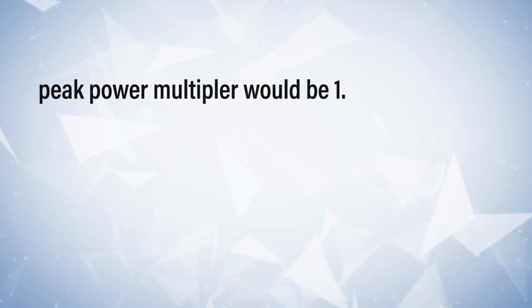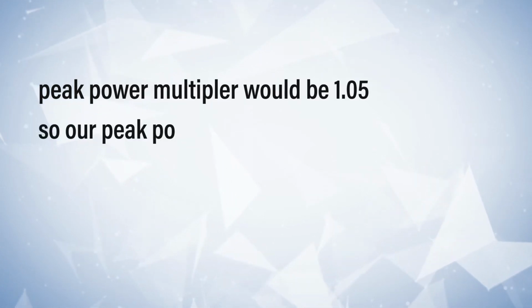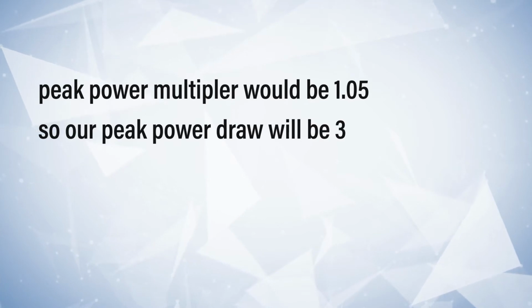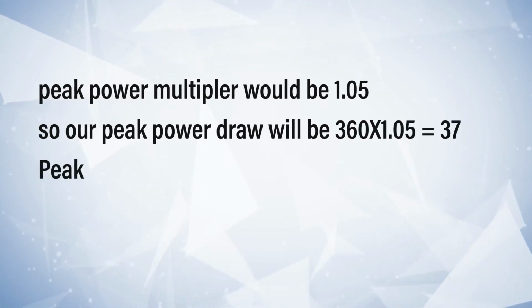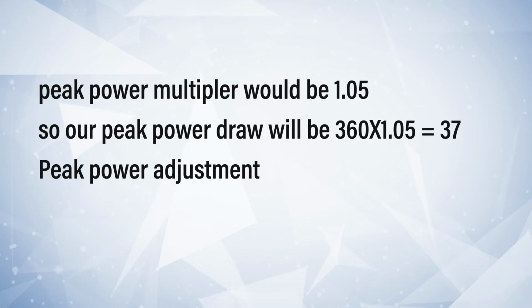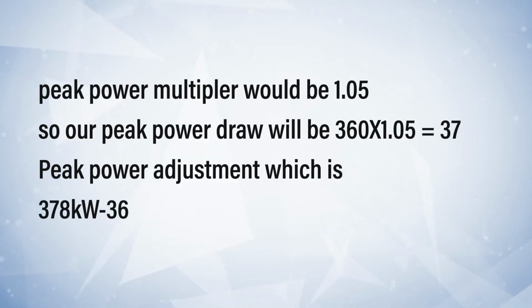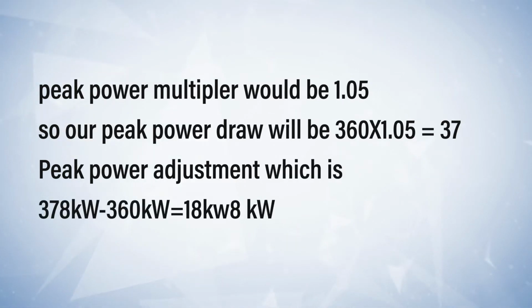With the total critical power load, now let's calculate the peak power adjustment that we would need during the peak consumption period. In general, we give 5% overhead for the full maximum usage. Now our peak power multiplier would be 1.05, so our peak power drawn will be 360 into 1.05, which is 378 kilowatts. Now by subtracting the critical load from the peak power drawn, we get the peak power adjustment, which is 378 kilowatts minus 360 kilowatts, which is 18 kilowatts.